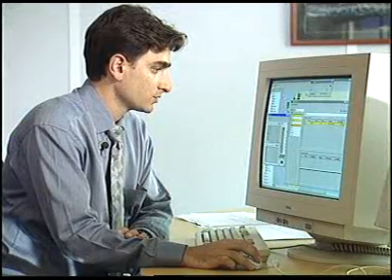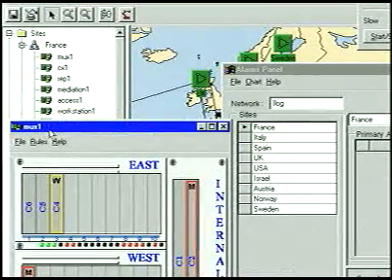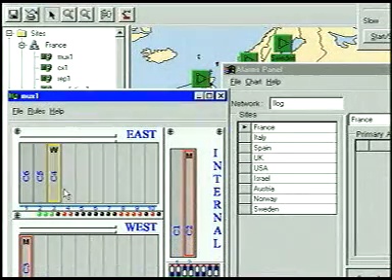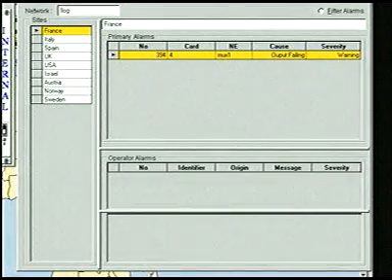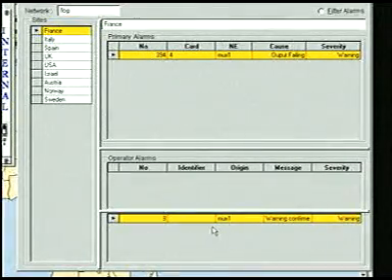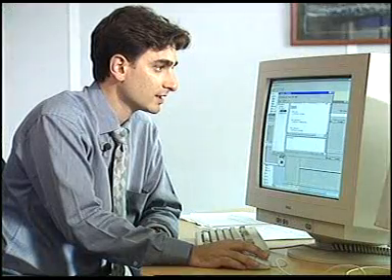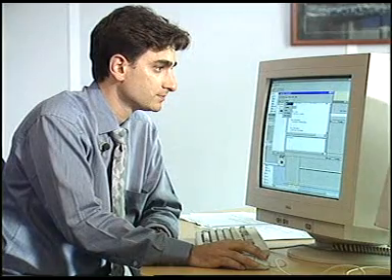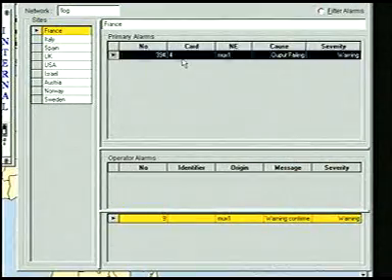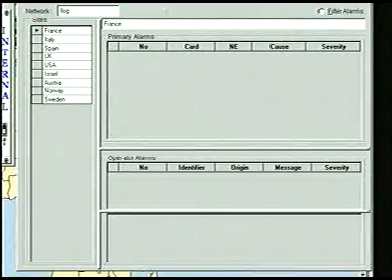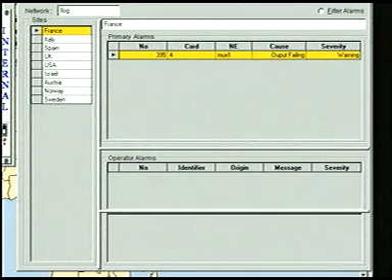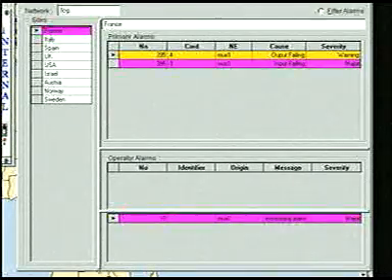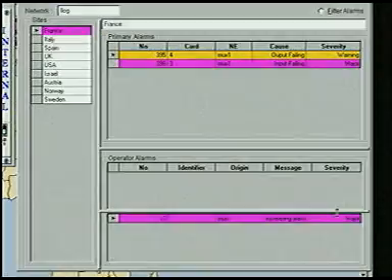In order to trigger the alarm, let's place a warning alarm on this equipment. We will now wait 5 seconds. Here, we see that the warning alarm has been confirmed, since no alarm with greater severity was received during the elapsed time. Now, by creating a second alarm and inserting a greater status into the 5-second time frame, we see that the rule has triggered the action for showing our special increasing alarm message.